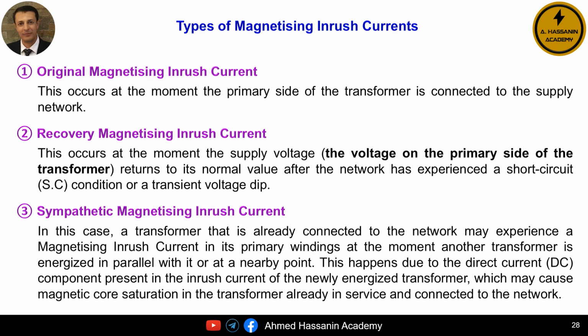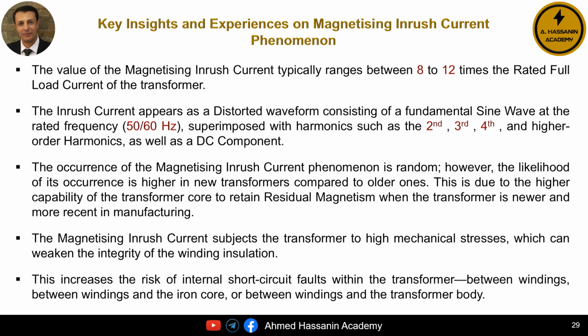The third type is the sympathetic magnetizing inrush current, which occurs in a transformer that is already in service and energized as a result of energizing another transformer connected in parallel or located nearby. Before we talk about the most important solutions to overcome the phenomenon of magnetizing inrush current, we will briefly and quickly discuss the key observations related to magnetizing inrush current.